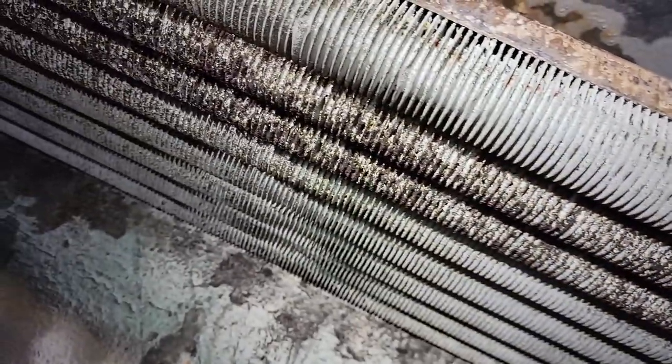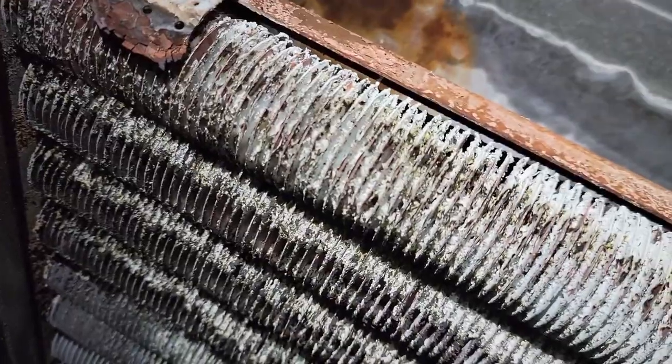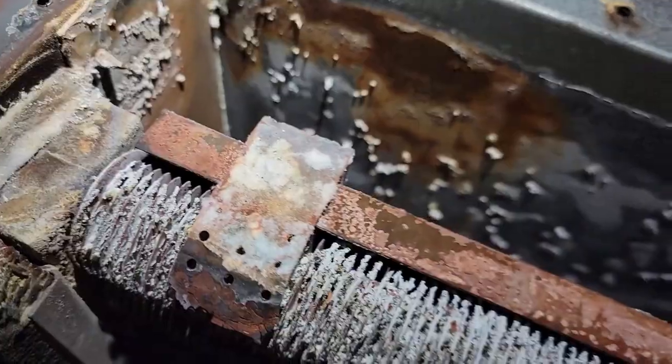That allowed us access now to the heat exchanger, which has quite a bit of crud build up here on this side. This is where my flame disturbances were the most, and that's the first stage area. We're going to try to clean that up.